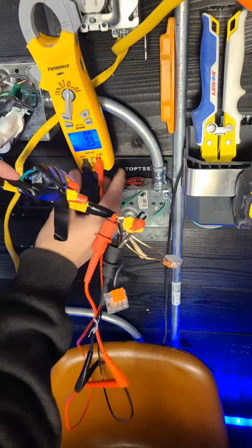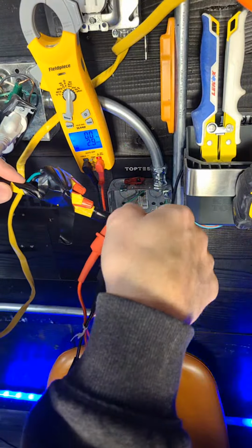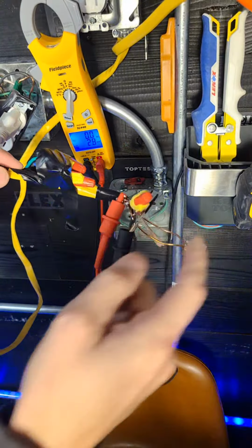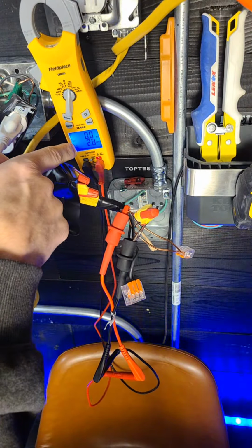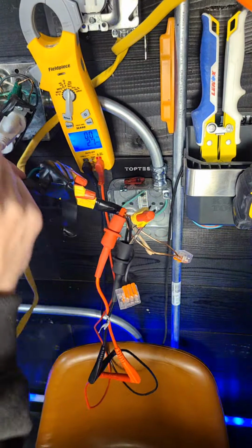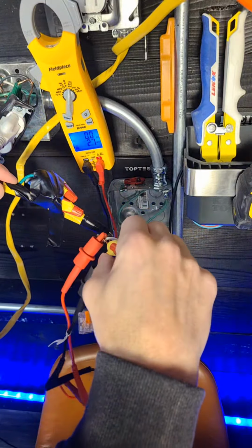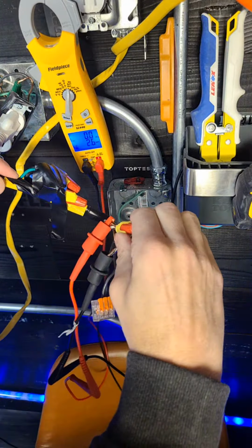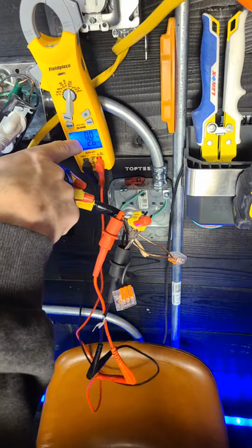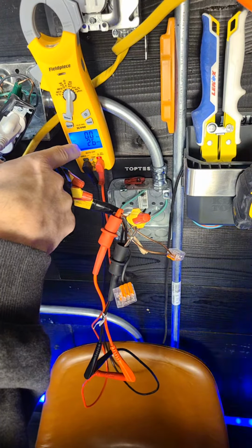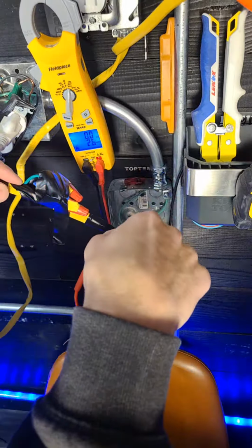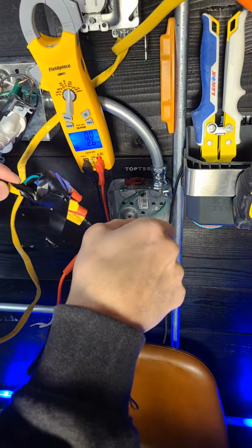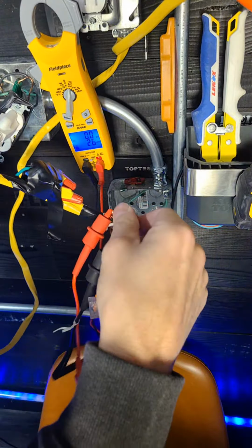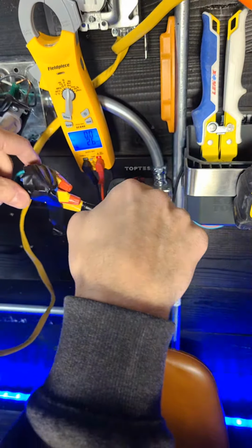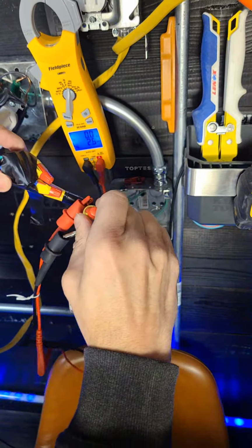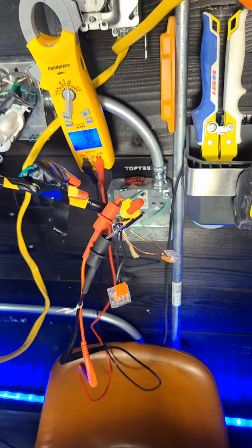2.9. We can probably change this real time just by tightening this a little bit more. See, we're down to 2.8. We're not going to go back up because I'm making the connection better. As I tighten this, you're going to see that connection get that much better. 2.6 now, and I'm going to continue to tighten this, see if I can get it to 2.5. But it's kind of dangerous. Got it to 2.5, there you go.